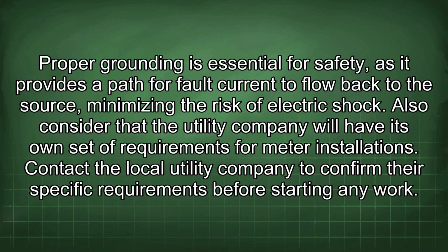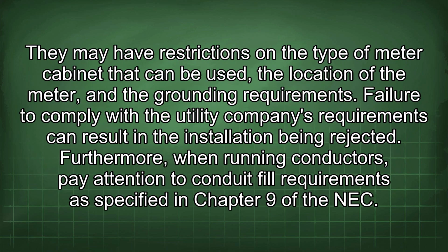Also consider that the utility company will have its own set of requirements for meter installations. Contact the local utility company to confirm their specific requirements before starting any work. They may have restrictions on the type of meter cabinet that can be used, the location of the meter, and the grounding requirements. Failure to comply with the utility company's requirements can result in the installation being rejected.